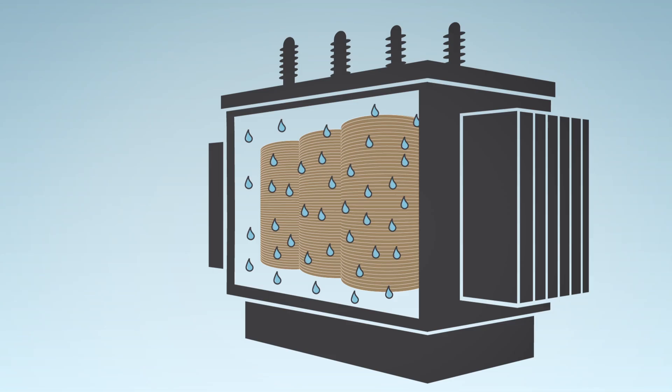The main thing preventing all these bad things from happening is the dielectric paper in the transformer windings. The real problem is that moisture will degrade the quality of the paper permanently and irreparably.